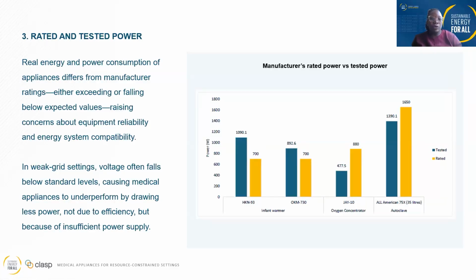When you look at the manufacturer's rated power and the tested power consumption in healthcare facilities, one big reality is that the actual power draw of appliances rarely matches what the manufacturers claim. In most facilities we visited, appliances consumed either more or sometimes less than the rated values. This raises concerns about the reliability of equipment and its compatibility with the energy system we design. On average, power drawn during testing was consistently above or below the manufacturer rating, as you can see from the graph — some appliances above, and some well below the rated power.